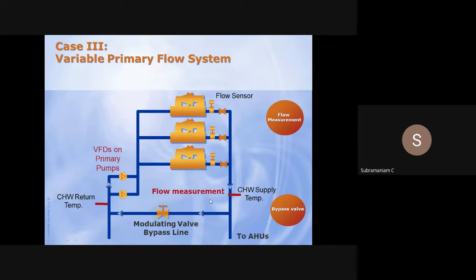Otherwise, we will be damaging the chiller, because what happens is we are varying the flow through the chiller, and with every chiller manufacturer, there is a minimum chilled water flow rate. They do not want that to go below a certain value. So we have to take care. If we go below that, the evaporator tube will burst. Then water will go into the compressor from the evaporator, and then we will have a problem with the compressor refrigeration cycle there. And we have to have flow measurement.